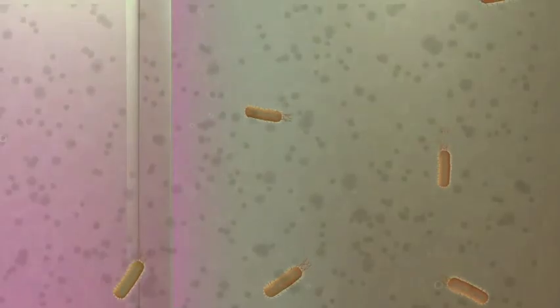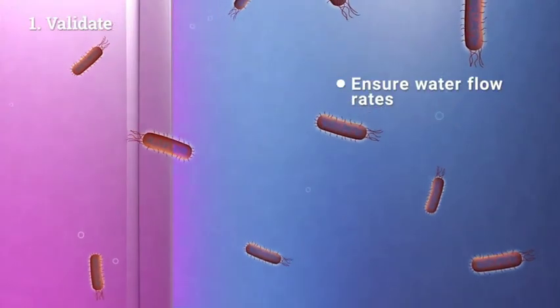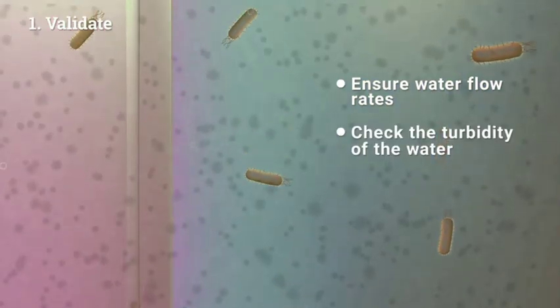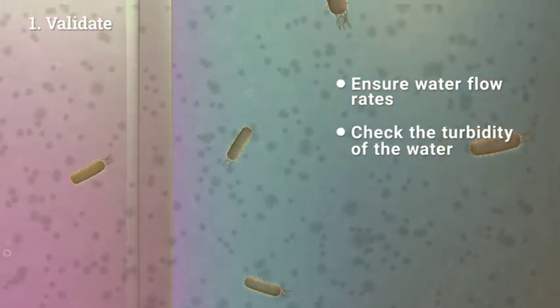If water is too dirty or turbid, the UV light won't be able to pass through to work properly. Check water flow rates so that water is not moving too fast, and also check the cloudiness or turbidity of the water to ensure the UV light works effectively.